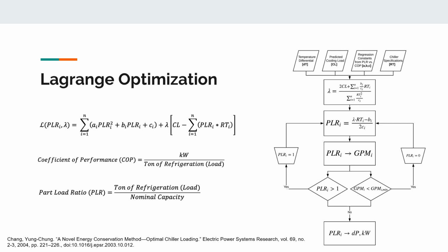The constraint for our Lagrangian model is the cooling load CL from our predictions made by our neural model equal to the sum of the individual chiller's loads, PLR times RT, while satisfying the minimum and maximum chiller thresholds such as flow rate and maximum capacity. The Lagrange algorithm inputs various parameters such as differential temperature and predicted cooling loads, which then get applied to the Lagrange multiplier lambda. Lambda is used to find individual chiller PLR and is converted into flow rate. If the flow rate and PLR values of individual chillers satisfy the operating limitation, then PLR values are converted to differential pressure for operation accessibility and total energy usage is logged.